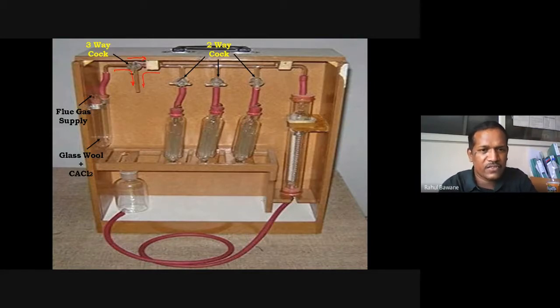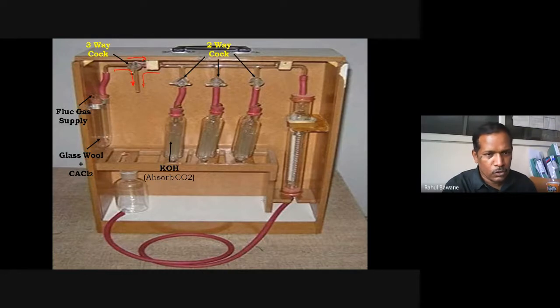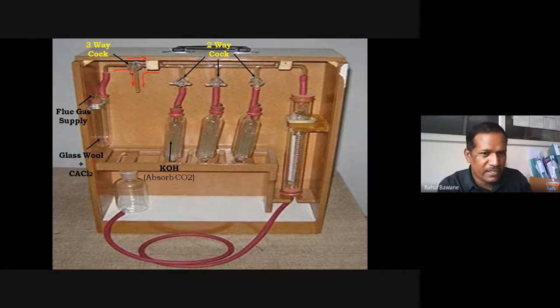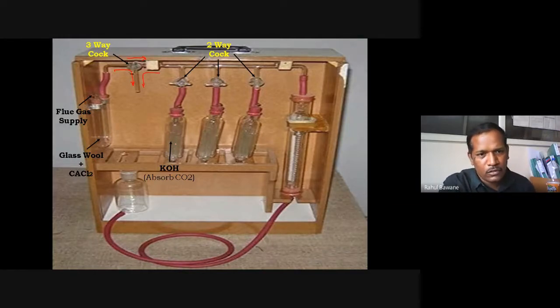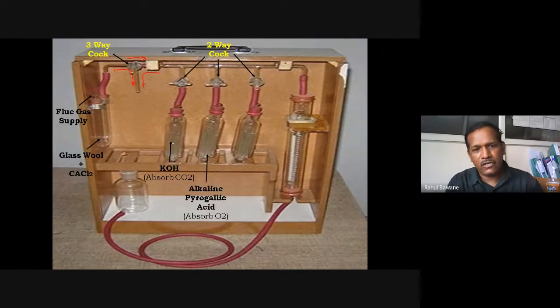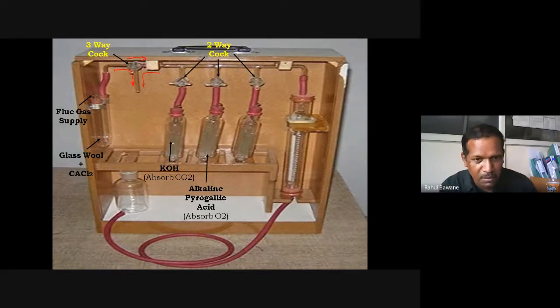The glass bulbs are not empty. Each glass bulb contains a different solution. The first glass bulb contains KOH solution. KOH has the tendency to absorb CO₂ gas. So if the exhaust flue gas has CO₂ content and passes through this first glass bulb, the KOH solution will absorb that CO₂.